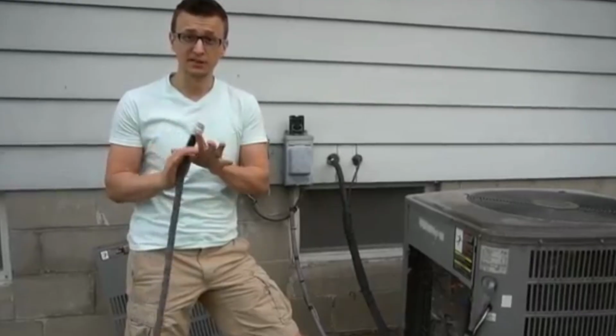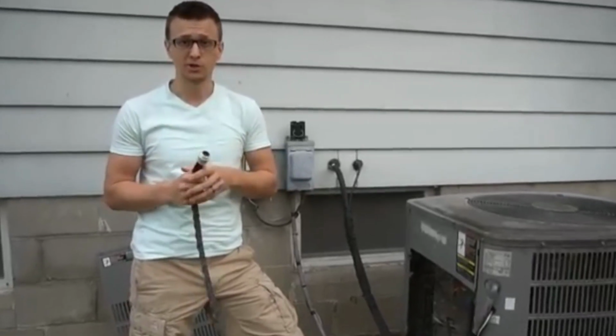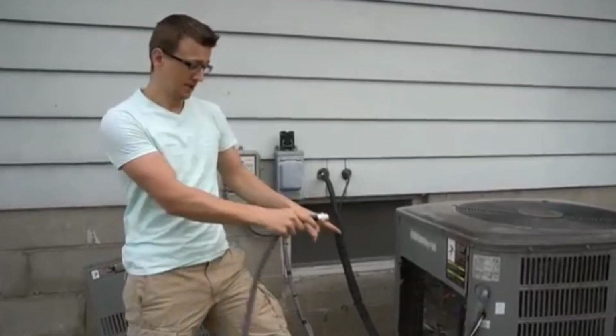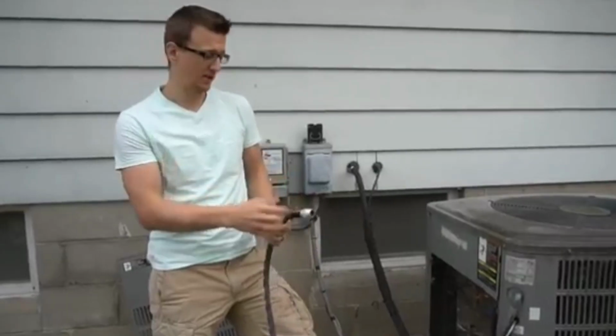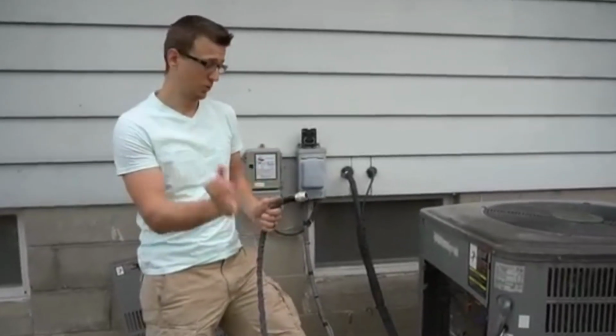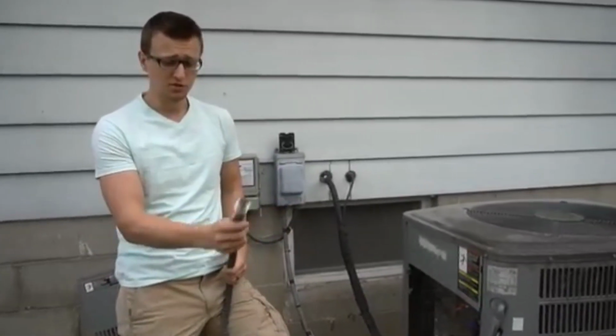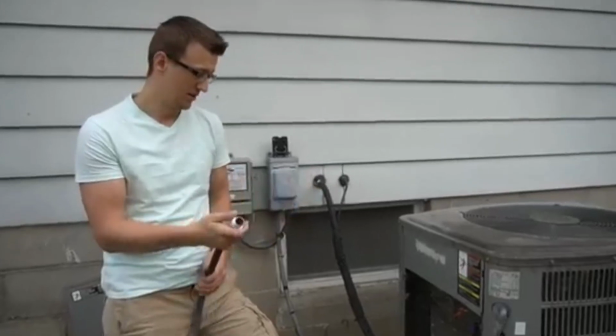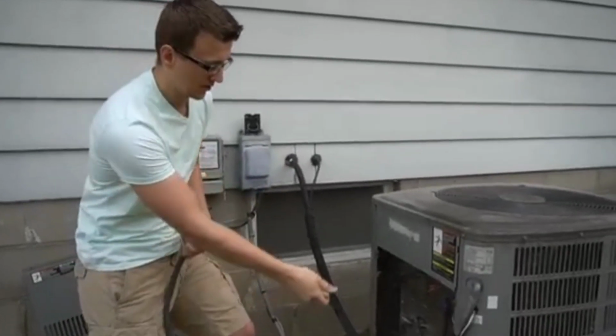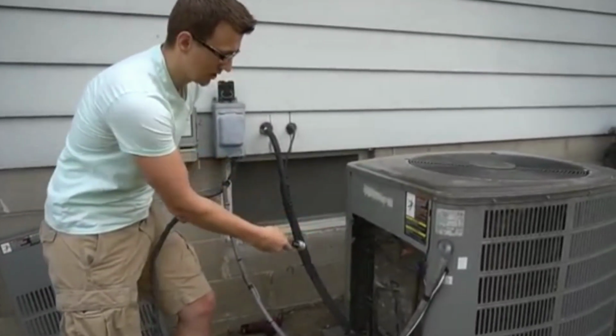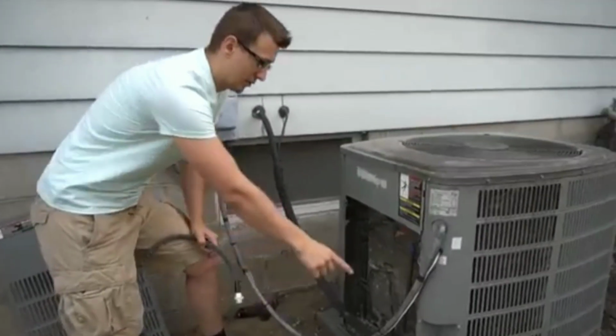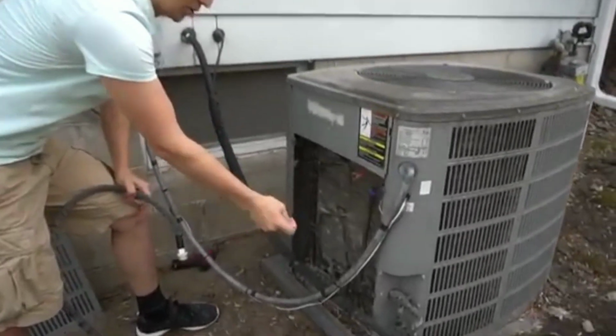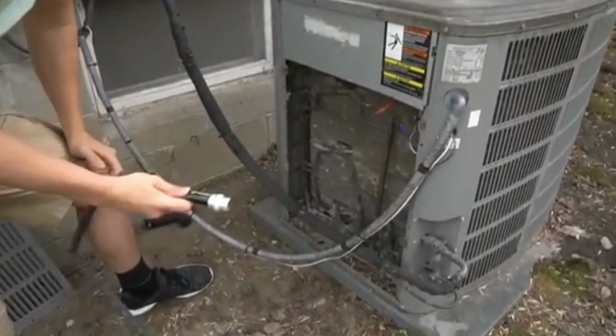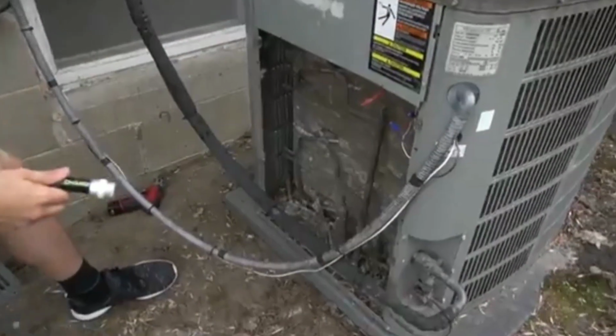And by all means, do not use a power washer or a pressure washer, because those fins are pretty flexible, and if you use a lot of pressure, they will all bend. But just regular water pressure is good. I'll just cover it up with my thumb and just spray down my coil. If you want to go an extra mile, you can also vacuum it out or blow it out first before you start washing. I'll just wash it for now.